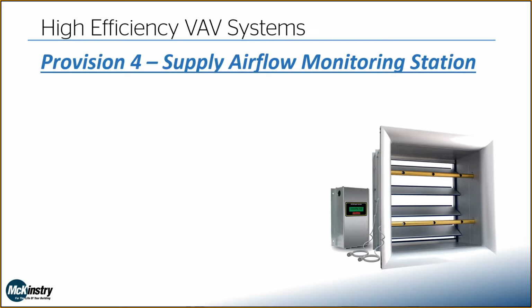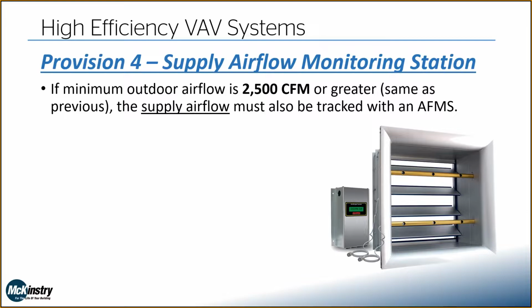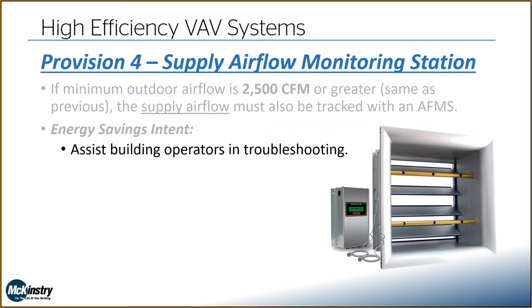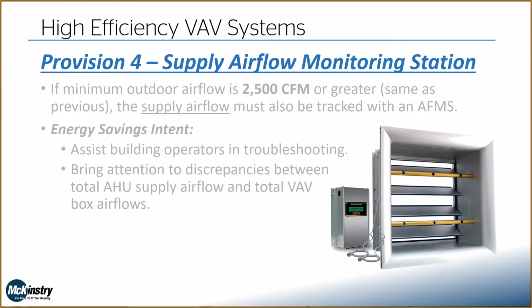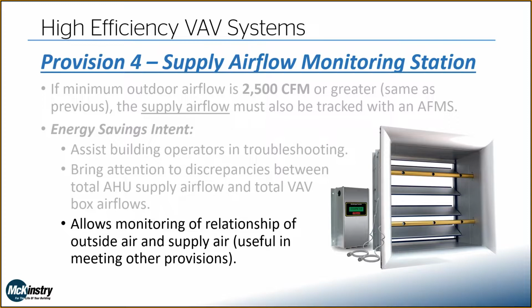Next up, we have supply airflow monitoring. This has the same trigger as the previous provision. If our minimum outdoor airflow is 2,500 CFM or greater, we also must track the supply airflow. As far as the savings intent, this is going to assist our building operators in troubleshooting. For example, if we have a discrepancy between our total air handler supply and our total VAV box supply airflows, this will help bring attention that something is wrong. Additionally, this allows monitoring of the relationship between outside air and supply air, in terms of what percent of supply air is outside air. This is going to be useful in meeting some of the other provisions to come. To the right there is an example of an Ebtron Gold flow meter, which would be a fairly common airflow monitoring station.